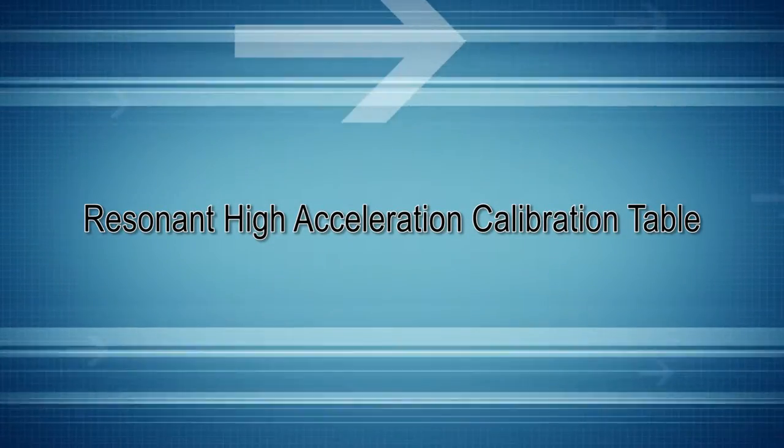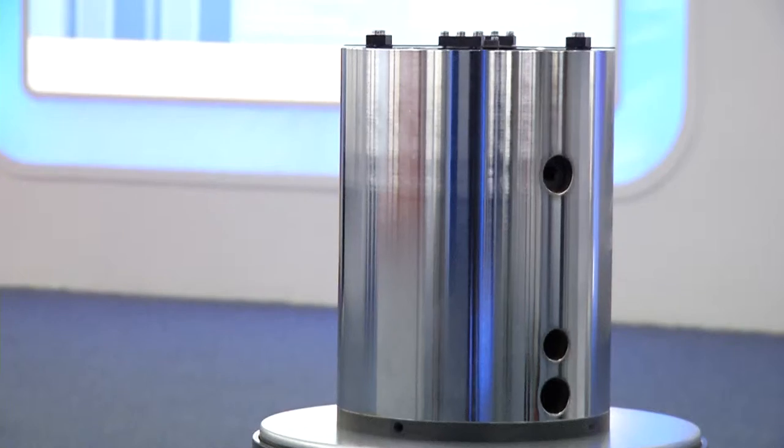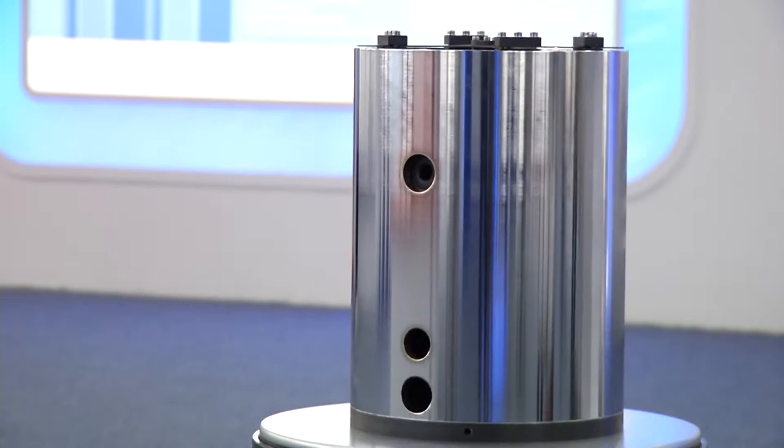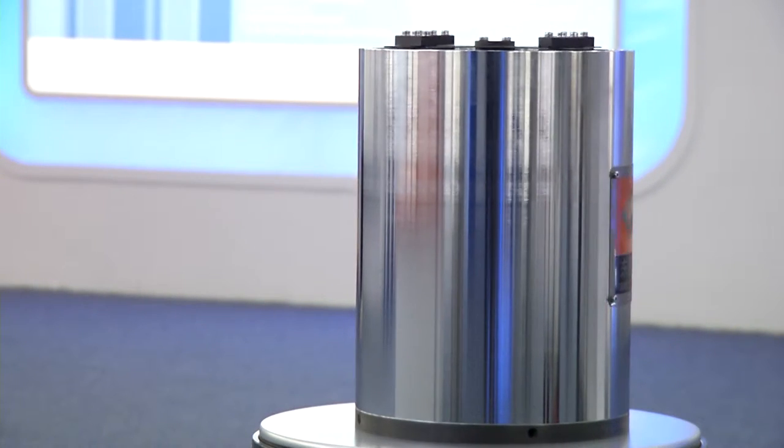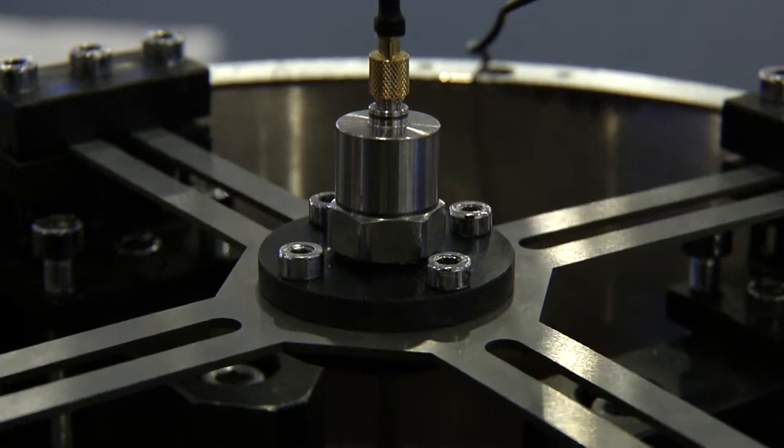Resonant High Acceleration Calibration Table is a precision calibration device. Its maximum acceleration is up to 500 G. Usable frequency range is from 10 Hz to 500 Hz.